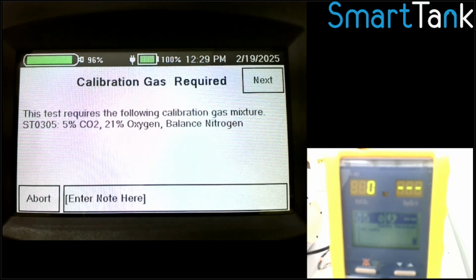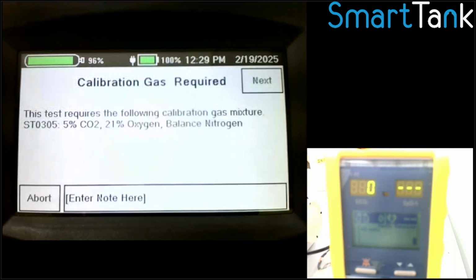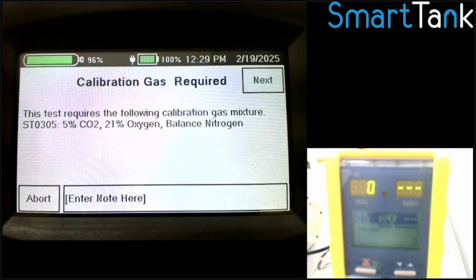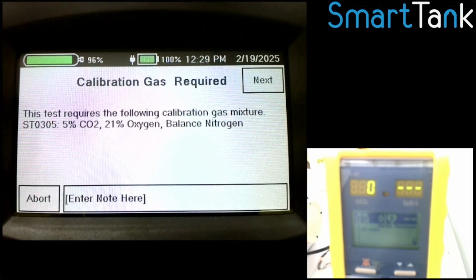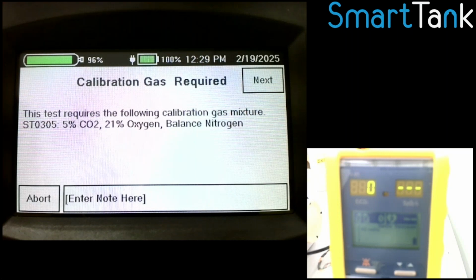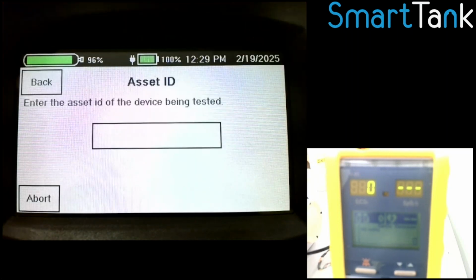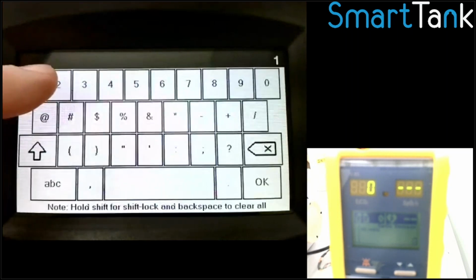Some sequences call for changing out from 5% to 10% or some other secondary gas, and again, it will make sure you do that correctly. Even the information on the gas bottle, like expiration date, lot number, all goes into the test report, and so it can track that. So I'm gonna hit next here. It wants an asset ID for the device I'm testing.